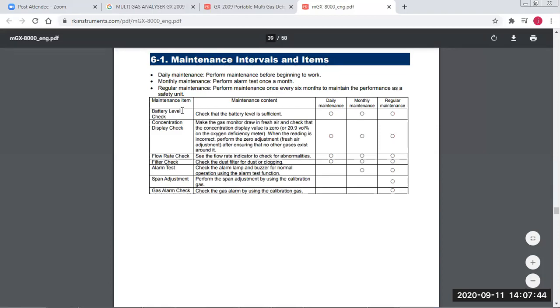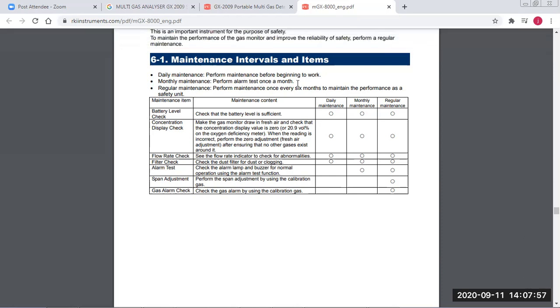So the maintenance of this equipment is that daily we have to check the power and battery, and whenever we are using calibration with air, then we have to do the alarm test once a month. The circuit is working properly. Then performance maintenance: calibration every 6 months and shop calibration every year, battery check, expiry, the sample gas and zero check, then the flow rate check as per the indicator, the filter check for no clogging, alarm test, buzzer test, span adjustment, and gas alarms check during this calibration.